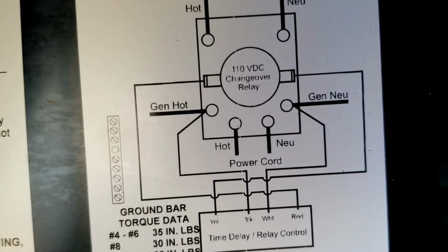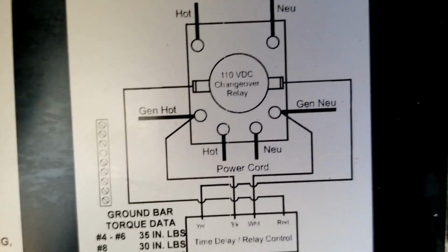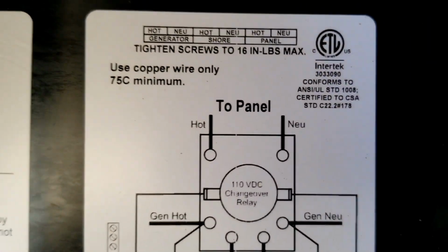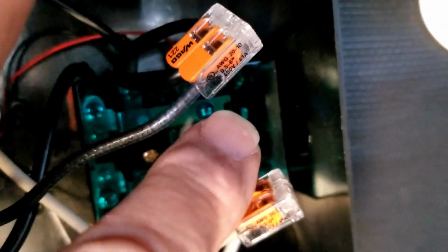So that will be our power cord coming in basically. And then this bottom line was the one that goes back out to that second 30 amp breaker, and it ties into the terminals up here at the end, or if we go back to our panel, it says panel 2. So essentially the power is coming in on this wire, going through this transfer switch, and going back out on this wire to our panel.